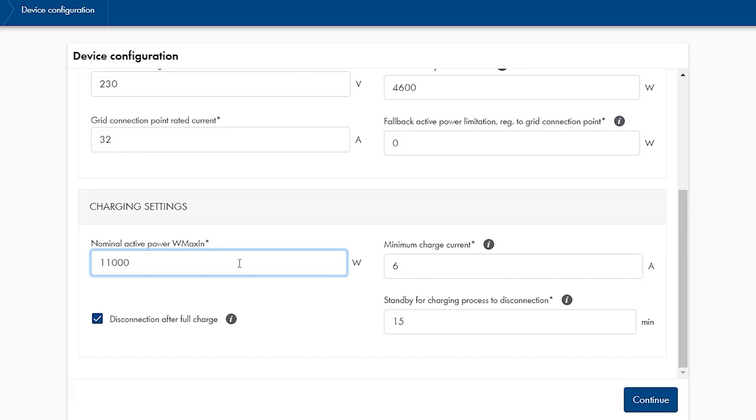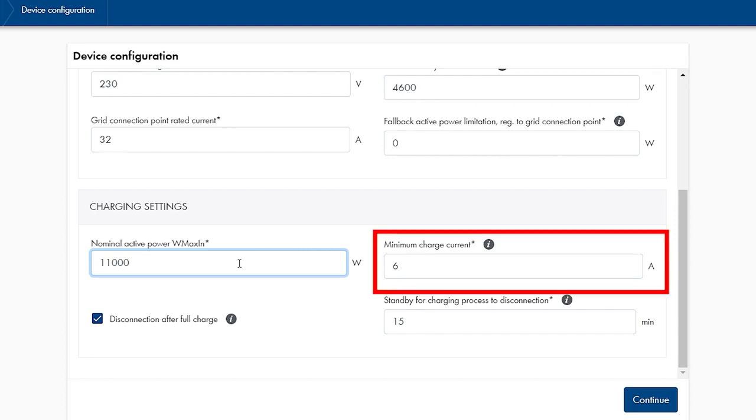The circuit breaker for the SMA EV charger in the sub-distribution must match these settings. According to the standard, electric vehicles usually start charging from a minimum charging current of 6A.